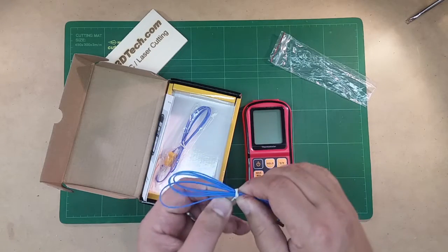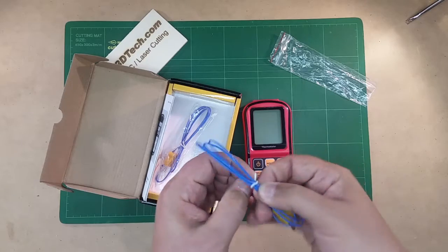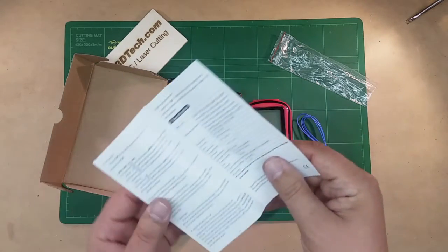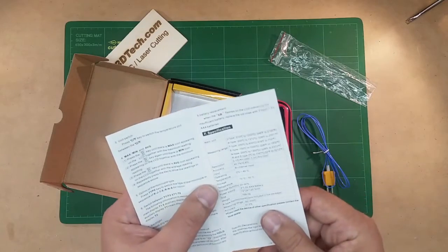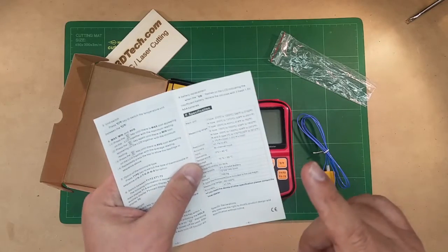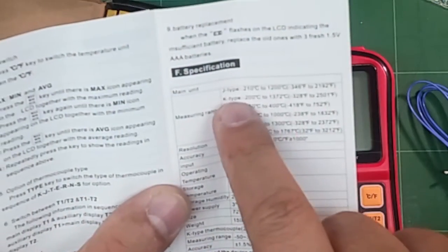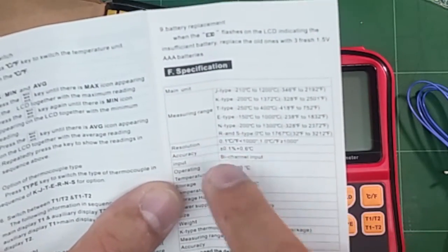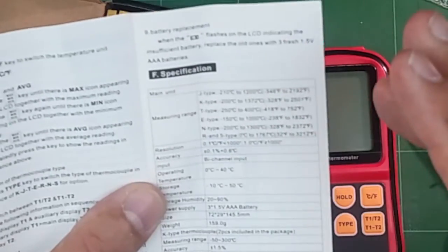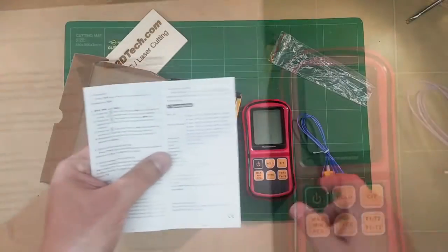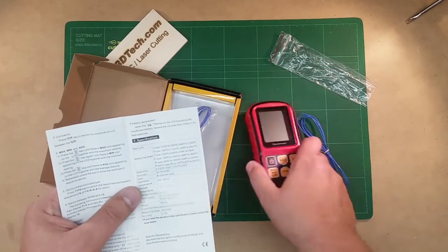Now, apparently, I think this will take... Yes, yes. So what I like about this is there are different types of probes. So there are J, K, T, E, N, and R probes. Each one of these type of thermocouples have a different signature or curve, and this is how the little microprocessor in here knows how to read the temperature.